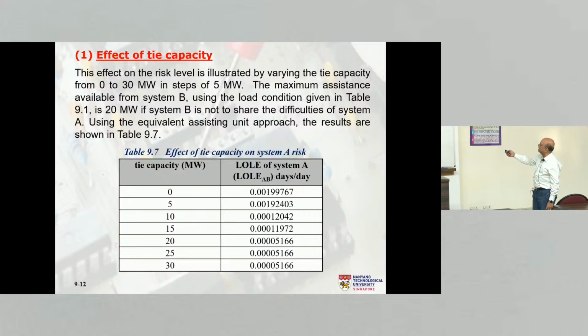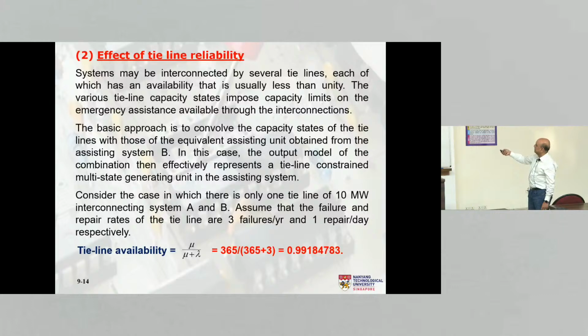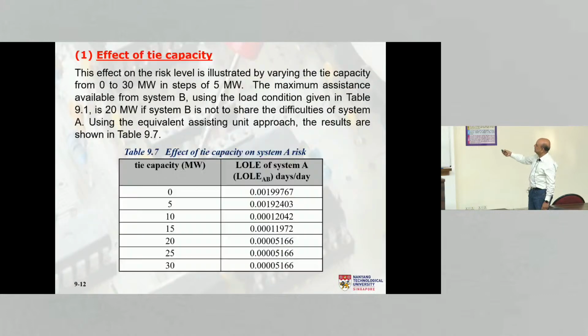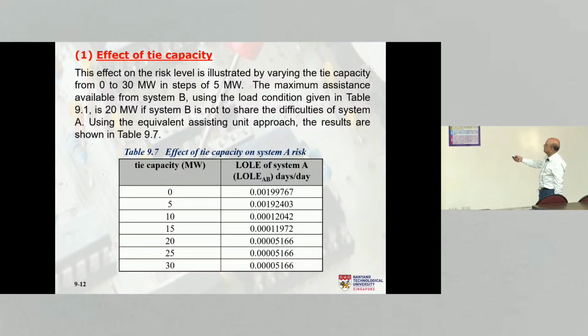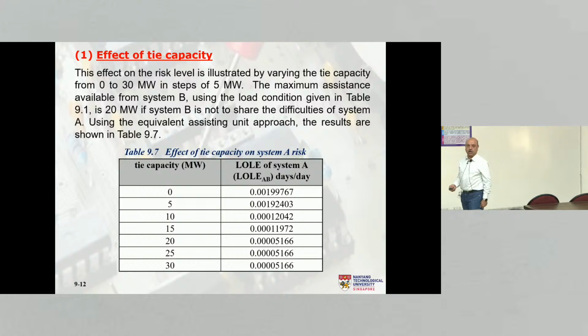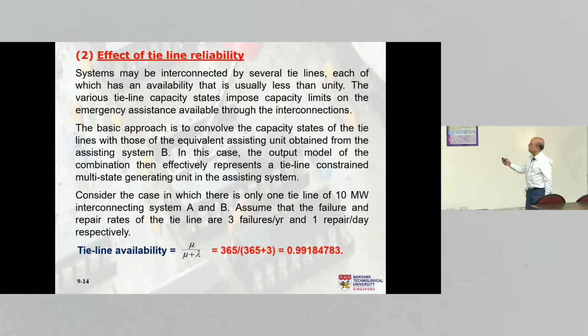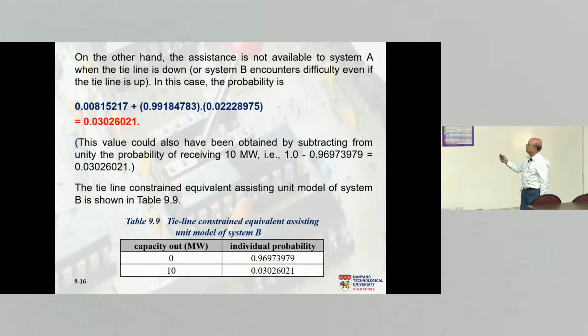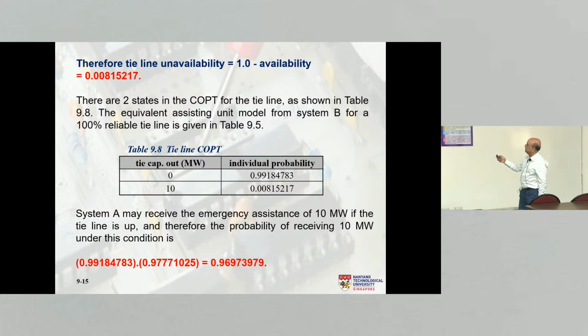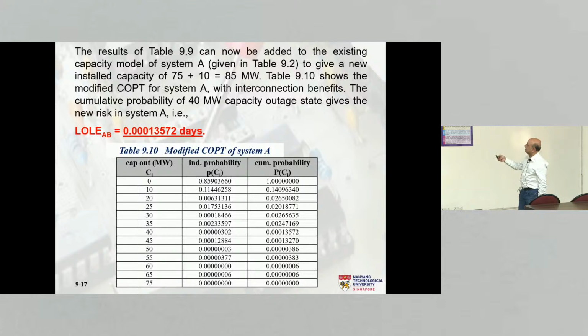What was the risk before? No, 10 megawatts, so more than 15. 0.00011972. So you can see that the benefit has changed now when the tie line is not fully reliable. Okay, we have done this. So this is the new LOLE. Correct?